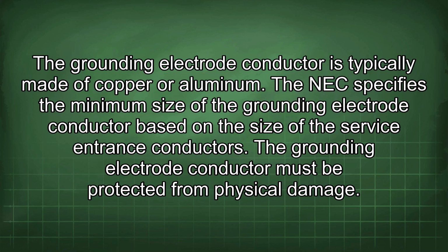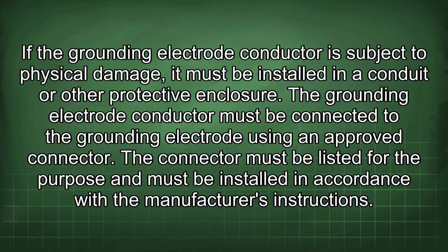The grounding electrode conductor must be protected from physical damage. If the grounding electrode conductor is subject to physical damage, it must be installed in a conduit or other protective enclosure. The grounding electrode conductor must be connected to the grounding electrode using an approved connector. The connector must be listed for the purpose and must be installed in accordance with the manufacturer's instructions.